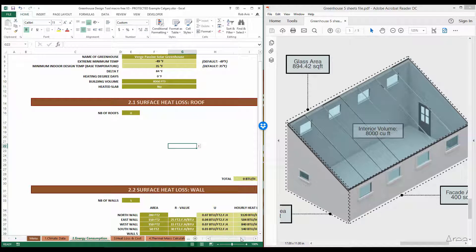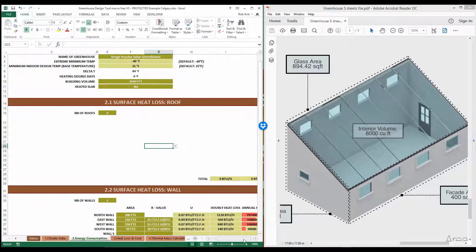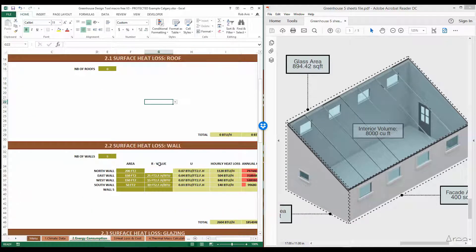Some greenhouses will have a roof surface, and if they do, you'll enter that information with the appropriate R-value as well as area. Next, we're going to go to section 2.2, surface heat loss for walls. For this particular part of the tool, you'll notice that we have four walls — one, two, three, and four — which are the south, east, north, and west walls.